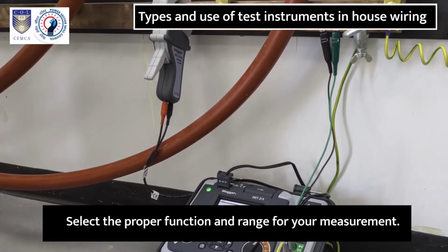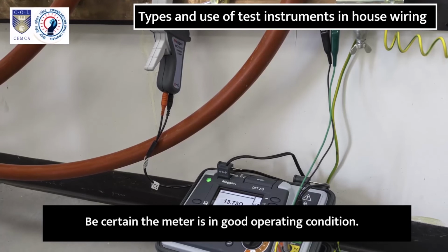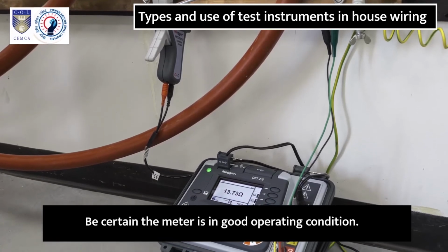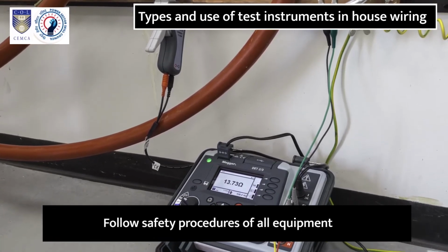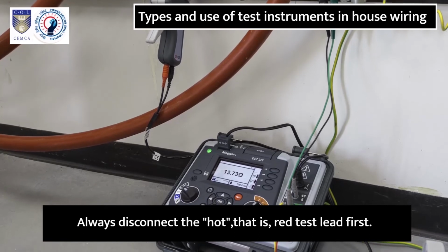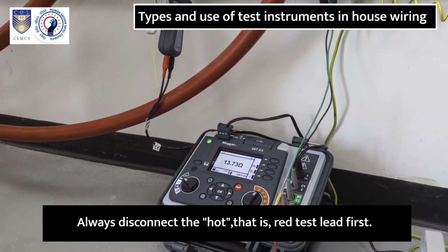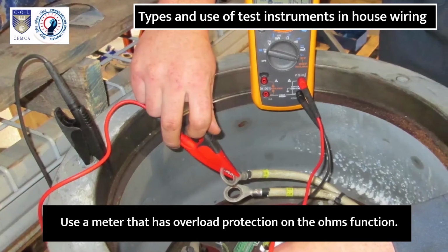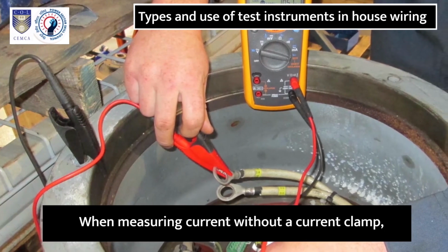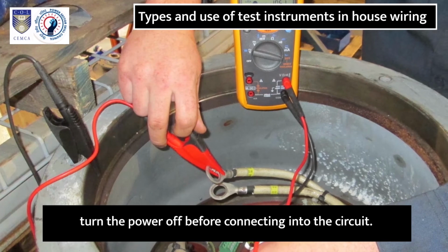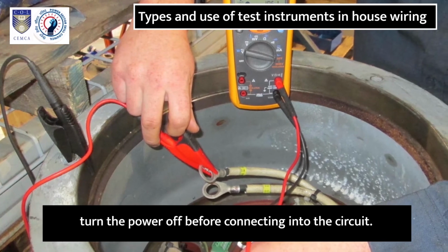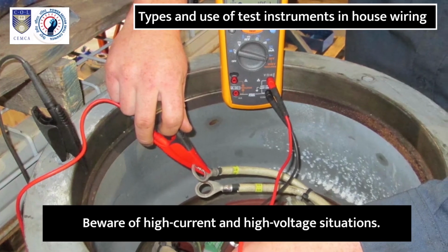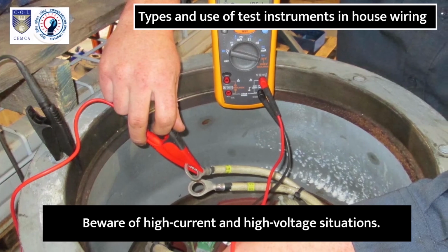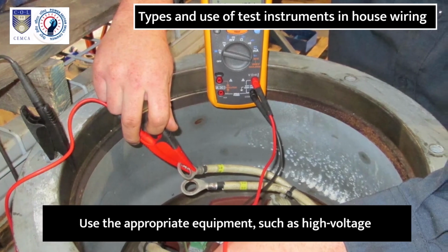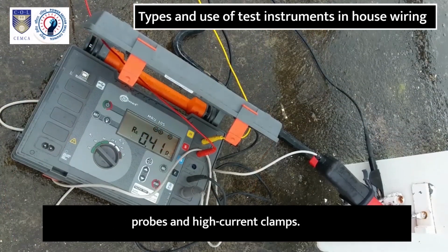Select the proper function and range for your measurement. Be certain the meter is in good operating condition. Follow safety procedures of all equipment. Always disconnect the hot, that is red, test lead first. Don't work alone. Use a meter that has overload protection on the ohms function. When measuring current without a current clamp, turn the power off before connecting into the circuit. Beware of high current and high voltage situations. Use appropriate equipment such as high voltage probes and high current clamps.